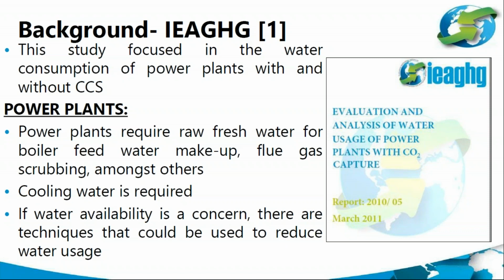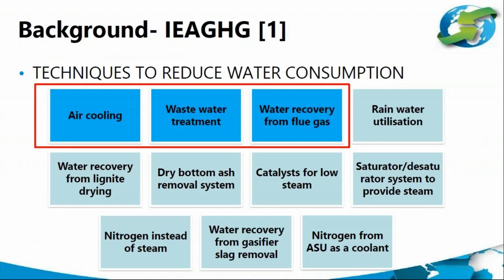If water availability is a concern, we wanted to explore which techniques are available to reduce water usage in power plants and power plants with CCS. In this study, we explored different techniques to reduce water consumption, such as air cooling, wastewater treatment, water recovery from flue gas, rainwater utilization, water recovery from lignite drying, dry bottom ash removal systems, the use of catalysts to decrease steam consumption, saturator-desaturator systems to provide steam, using nitrogen instead of steam, water recovery from gasifier slag removal, and use of nitrogen from an air separation unit as a coolant.